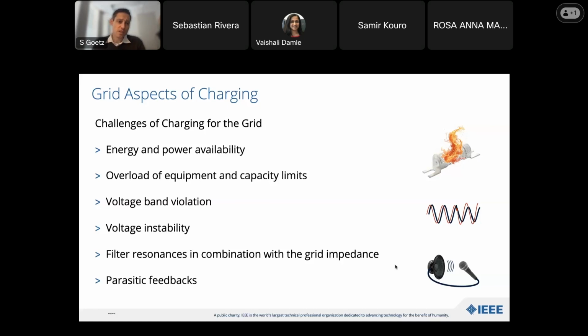But you also have dynamical problems. It starts with voltage band violations. That means you turn on your charger, the voltage of the grid, the AC voltage, whatever, 230 volts or 110 volts, comes down during the entire time you draw current and goes back up when you stop charging. That has become a major problem because grid impedance is rising rather than decreasing due to the massive electronification of everything. We'll have a look at that in a second.